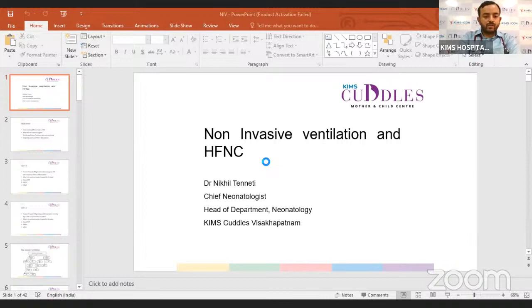Practical application: although HFNC is defined as flows greater than 1 liter per minute, routinely flows are initiated at 5 to 8 liters per minute, and as the baby shows improvement, they are weaned gradually to flows of 2 liters per minute, after which it is stopped. So this is a setup. This is a picture demonstrating the HFNC circuit that is routinely used in NICUs. The first one is the HFNC through Fisher and Paykel, in which we can see an air oxygen blender along with an infant flow meter.